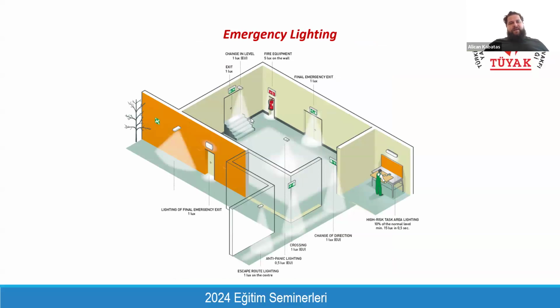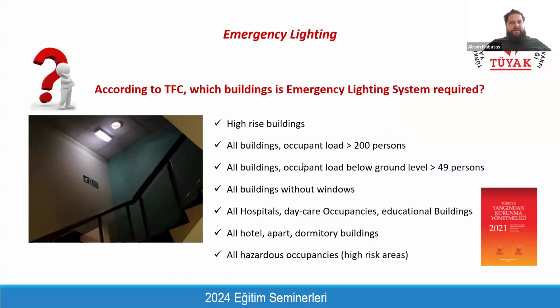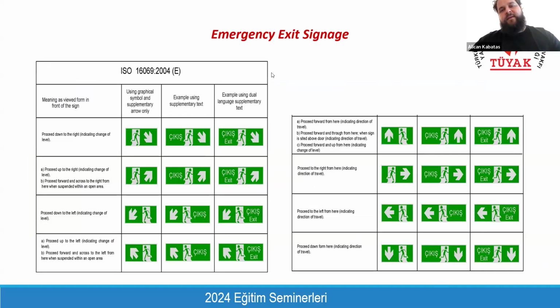And also we have emergency lighting. This is a good example to understand the main principle of emergency lighting. The exit routes, the fire and life safety equipment, and the main technical rooms should be equipped with an emergency lighting system so that in case of any kind of energy loss, these areas can be found by occupants and egress can be done safely. In high-rise buildings and below ground level with occupant loads of more than 50 people, or if the building has an occupant load of more than 200 people, dormitories, hospitals, and other high-risk areas should be equipped with emergency lighting fixtures as well. And exit signage is also important.